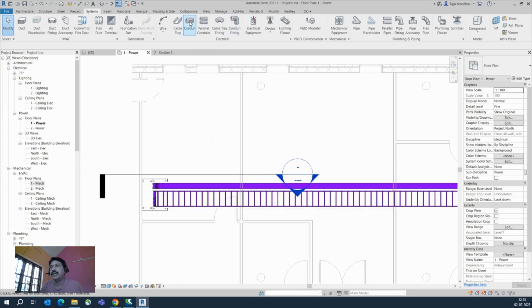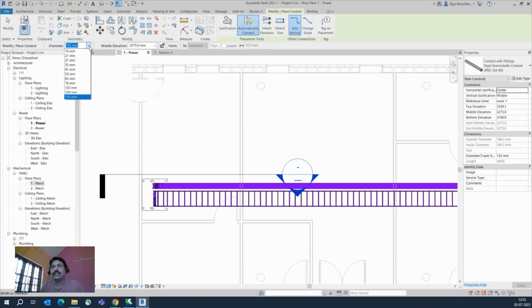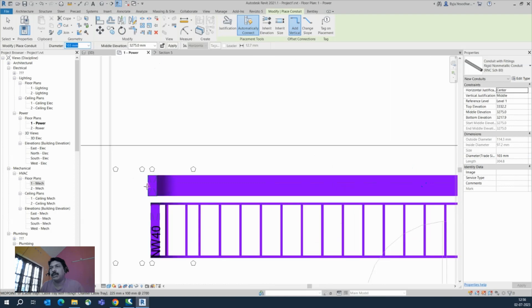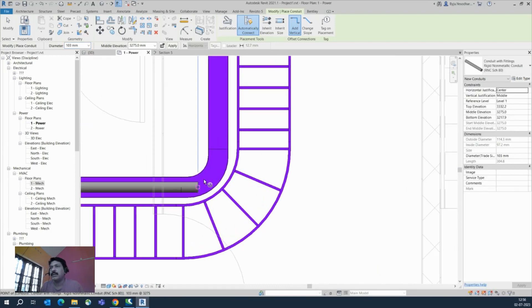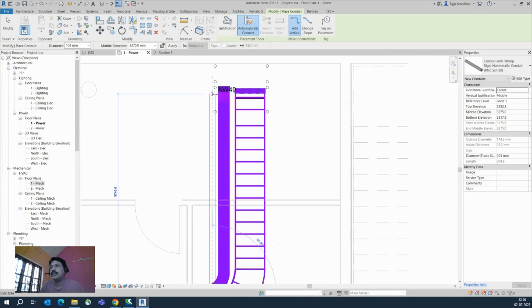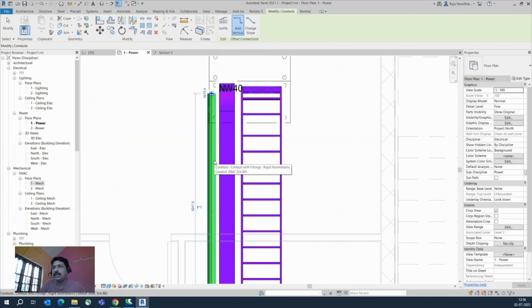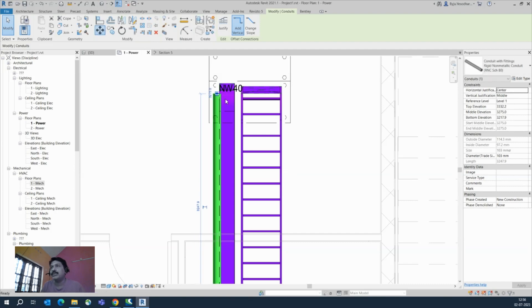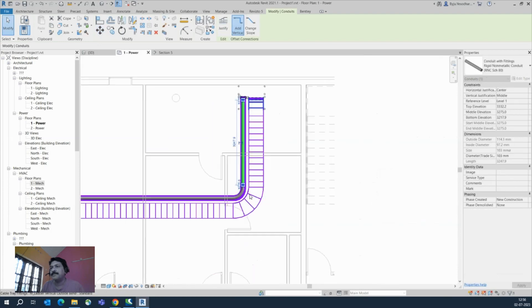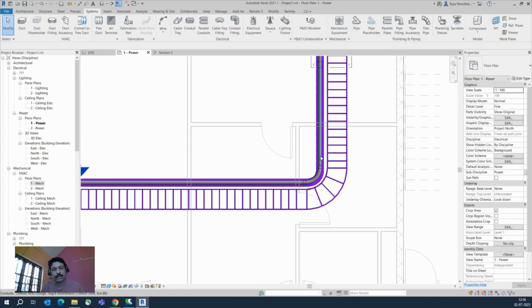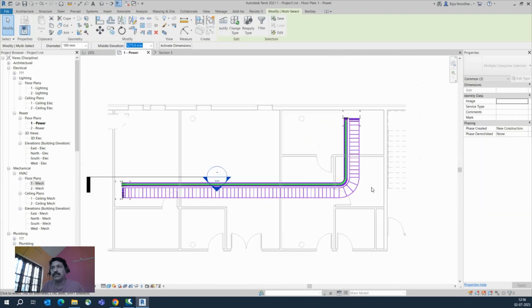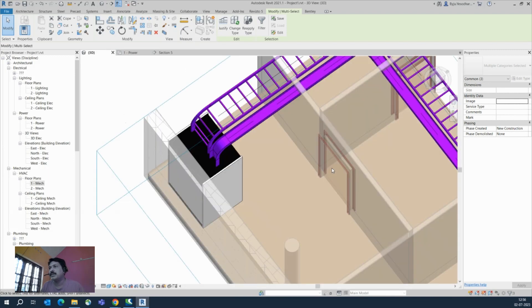Another example: you can also run conduits. Choose the conduit from the System tab, select the size, and specify the cable size you need. For example, I'll run a conduit like this and move it to the center of the cable tray. You can move it from here. To select just the conduit, press Tab and Enter — the conduits will be selected and you can see them running properly to the cable tray.